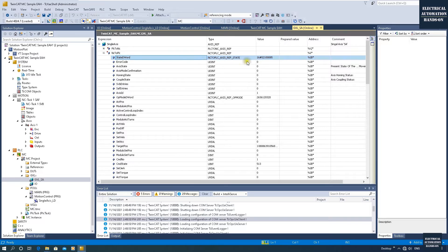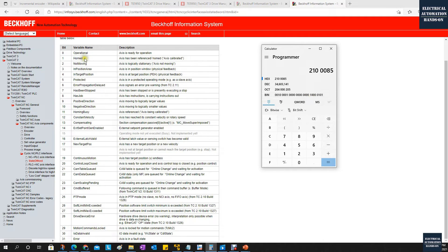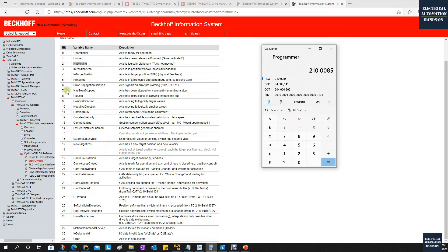For example, the StateDWORD is showing this value. We can use the calculator to translate it to binary. Open the calculator, go to hexadecimal mode, and type in 0x00210085. So from the individual bits and from this table, we can see: bit 0 is on, meaning this axis is operational — ready status. Because we just enabled it, this axis is not moving. And because this axis is at a stop status, bit 7 'HasBeenStopped' is showing as 1. Using those 32 bits we can know the basic status of our drive and of our axis.